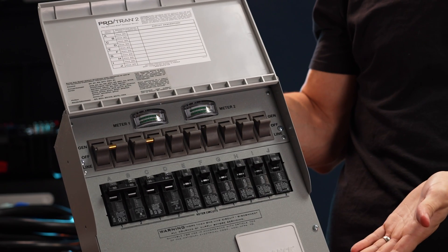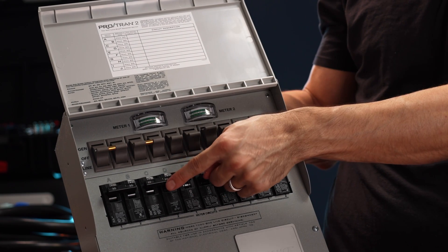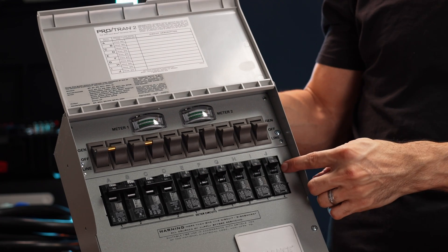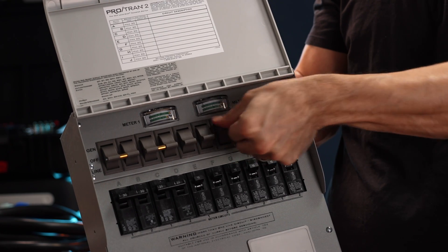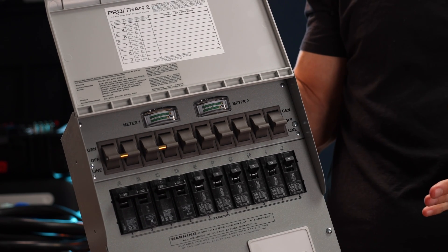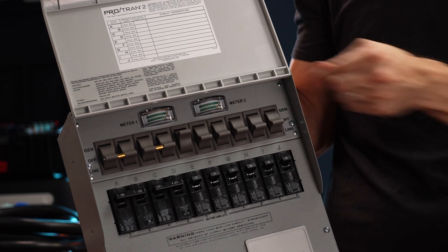We're still waiting for the electrician to show up. This is what the transfer switch looks like. We've got a 30-amp breaker connected to two of these, a 20-amp breaker also connected to these, and a bunch of 15-amp breakers for a total of 10 circuits.